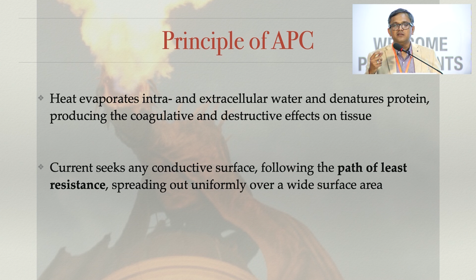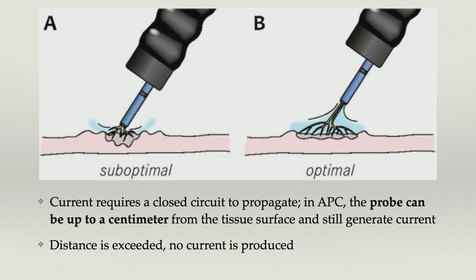If you move too close, it just becomes like an electrocautery and the transfer of energy does not occur. So that is a suboptimal technique. So what you need to do is always have a distance of about 10 millimeters, which is about 1 centimeter, between your probe and the tissue. And that's why we call APC the non-contact method of energy transfer.